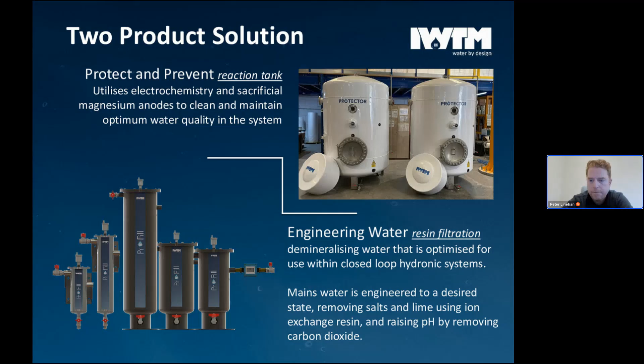And the second piece of equipment is our Profill, which engineers the water via resin filtration, demineralizing the raw water going into your heating and cooling system. It removes all your scaling minerals, such as salts, limes, and calciums. It removes your bacteria food, such as sulfate, nitrates and nitrites. It also removes the chlorides put in the water to make it safe for us to drink, but which attack the passivation layer of metals, allowing corrosion to take place. Effectively, we're demineralizing the water to achieve very low or zero conductivity water going into your hydronic system. So these 2 pieces of kit will engineer your water so it's in a non-corrosive state.